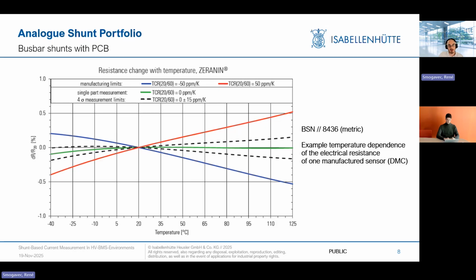Combined with the drift over lifetime that we often specify at 0.5% with the shunt itself, or measure at even lower than 0.3, we reach a total tolerance of less than 1% without taking into account any special customer requirements or application-specific topics or exceptional environmental changes, which is very fair to offer in today's market with the high accuracy demands. Making the BSN, for example, with especially the new TCR reduction concepts that I teased you before, one of the most accurate analog shunts to date.